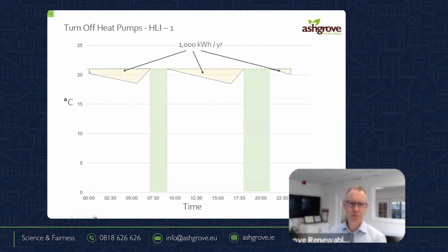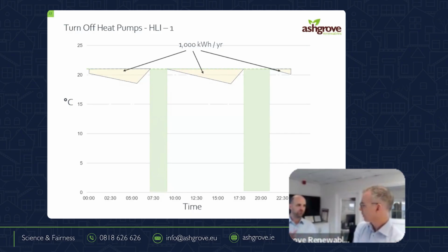Johnny and I came up with this fantastic way of portraying it here. We're just showing that the temperature will drop in the house if I turn off the boiler, over the day. This is overnight, actually. And then in the morning, I leave at whatever time this is. I need heat, in this case, from 7 o'clock to 9. But if I turn off the boiler, I leave, and the temperature starts dropping. And everything under that graph is energy I maybe should not have bought. Yeah, energy that you're paying for that you're not in the house, so you're not feeling any benefit from. So there's an argument to say that you shouldn't have bought that. Yeah. In that house that's well insulated, that's costing you €25 over the course of the year. So why would you bother turning it off?